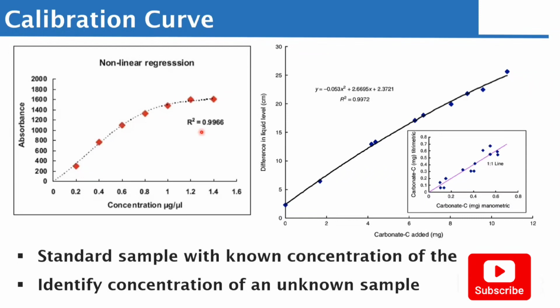Now, I'm also saying that even if it is the current one, if you notice that the person that performed the calibration did it in such a way that the R squared is a little bit far from 1, you can decide to repeat it to get it up to something very close to 1. I hope I'm able to make sense: the calibration we talk about is a curve, and that curve it generates gives the ranges in which the analyzer measures. Anything outside that range, the analyzer is unable to measure it. And that is why the QC might fail if it's a different lot number, as the case may be. Therefore, the calibration curve is a standard sample with known concentration of the analyte.